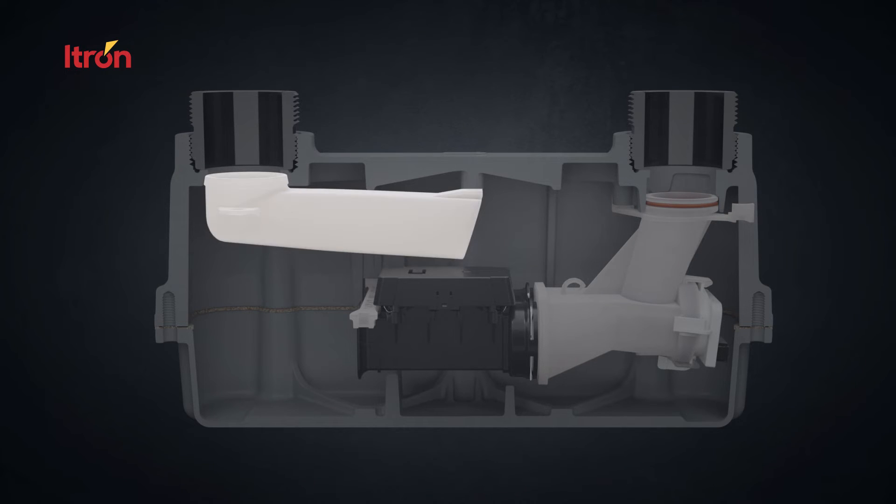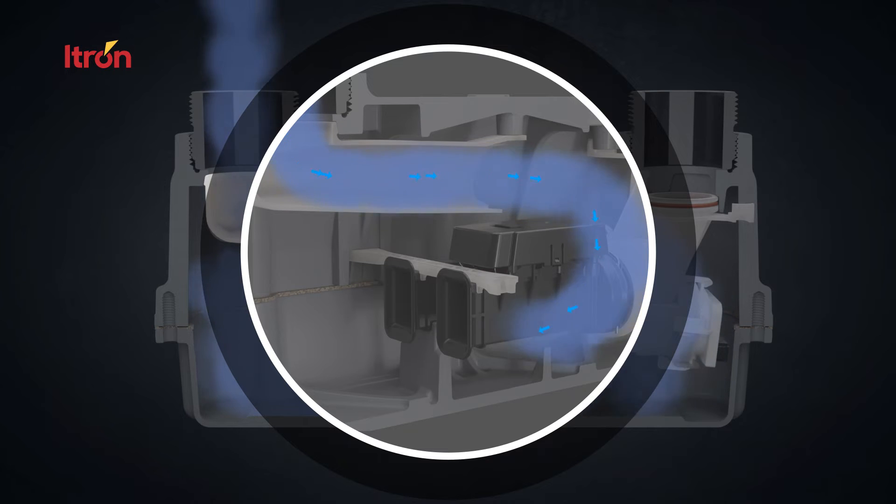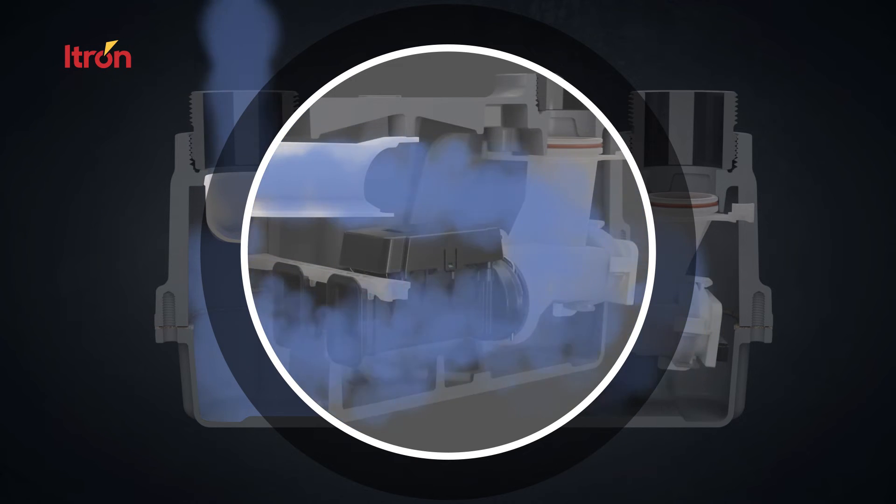The shape of the inlet tube diffuses the gas flow, including any particles, away from the UMU. As the gas flows, equal amounts pass through the UMU and the flow diverter, resulting in only 50% of potential harmful particles entering the UMU.